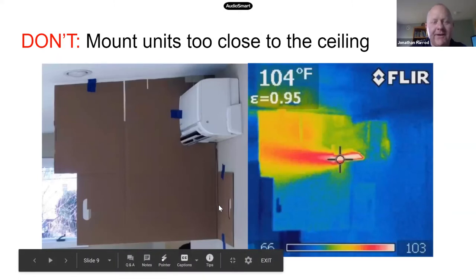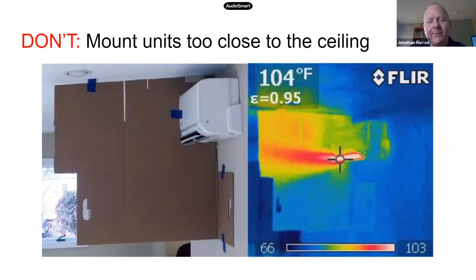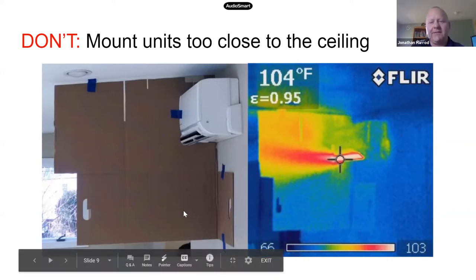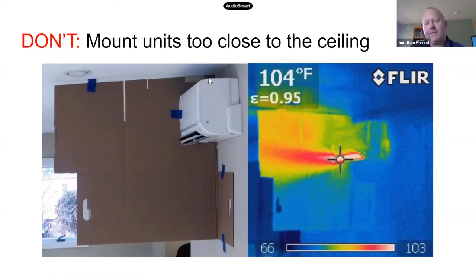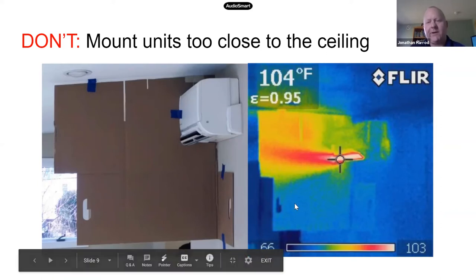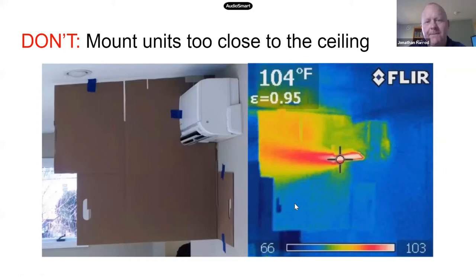This is a slide I thought was really interesting. This was done by Stephen Winter Associates, that are real building science geeks, and they did this very high-tech test where they taped a piece of cardboard next to a high wall unit and used an infrared scanner to look at the temperatures. And what they found, not too surprisingly, is that the air that's coming into the unit, these units draw the air in at the top, they pass it over the heat exchanger, and they blow it out at the bottom. The air that comes in at the top is not representative of the overall temperatures in the room. It's typically a few degrees higher.